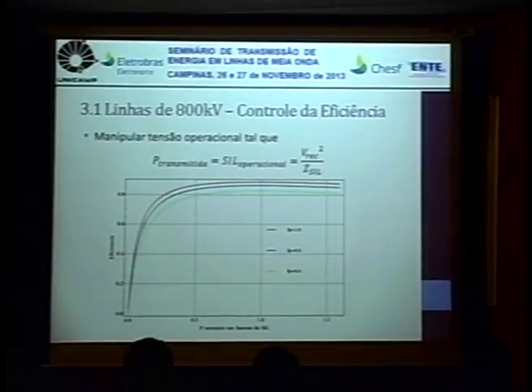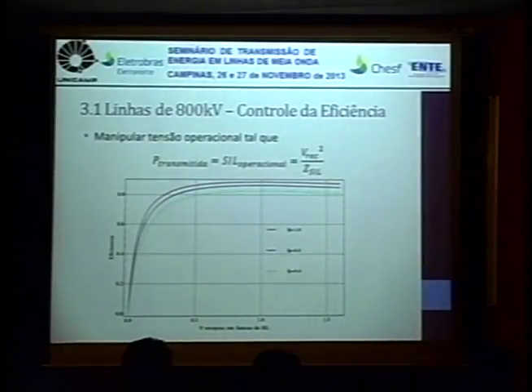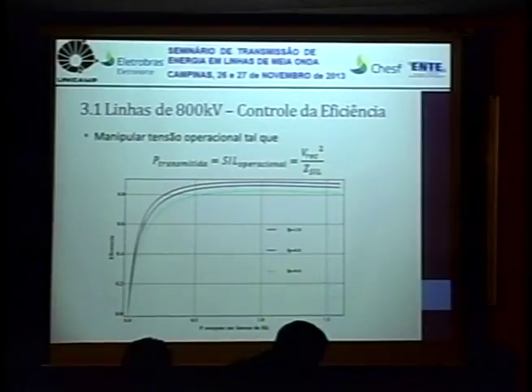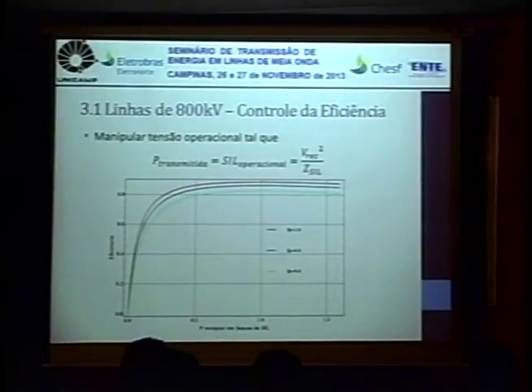We already know that the efficiency of a half-wavelength line is maximum at the characteristic power, and also when the power factor at the terminals of the lines is close to 1. So these were two aspects we worked with. What we are going to try to do is, regardless of the power level you want to transmit in the line, adjust the line so that the power level is as close as possible to the characteristic power. So our line was going to have a nominal voltage of 800 kV, but the operational voltage is going to vary. It can be 200, 400, 500, 600 kV, in a way that the power transmitted is as close as possible to the characteristic power.